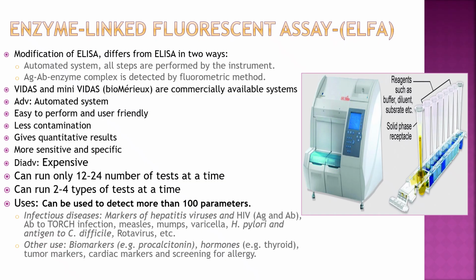Enzyme linked fluorescence assay. It is a modification of ELISA because it is a fully automated system. All steps are performed by the instrument. The antigen antibody enzyme complex is detected by fluorometric method. VIDAS and mini VIDAS are the systems available.